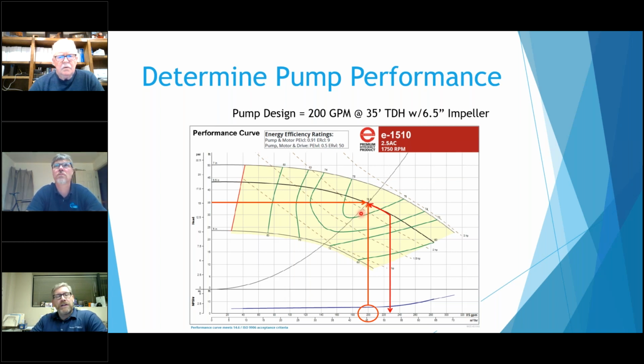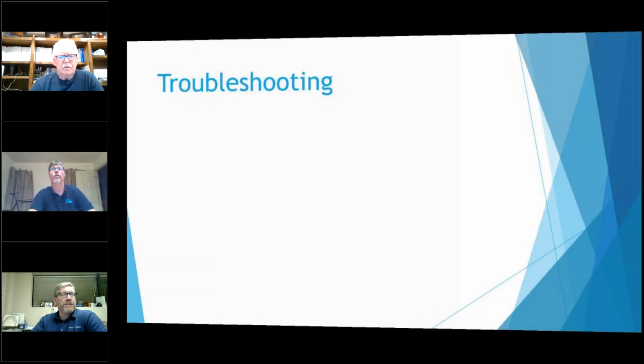What I did also want to point out, you can do a no-flow head test to see what impeller it is. Sometimes you don't know what it is, but if you close the discharge valve long enough to get your readings, you can kind of estimate what that impeller size would be. So if we close that discharge all the way down, now we know it's zero flow, and we come back up on the curve to where zero flow is. Your differential should be about 43, 44 feet or 20-pound differential. So you can kind of estimate what that impeller size is at that point. It's not exactly accurate, but it's close enough to give you an idea.